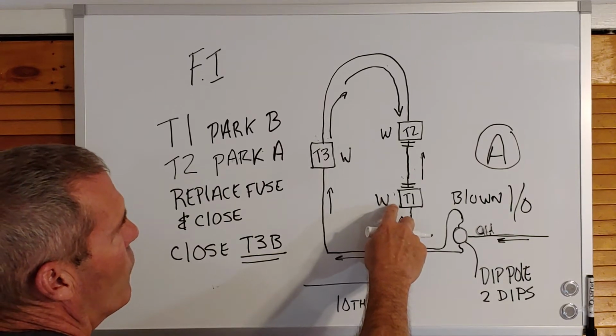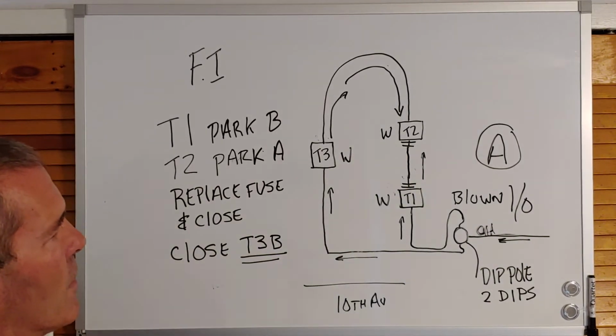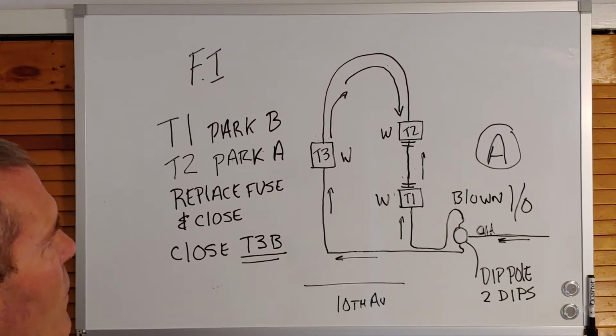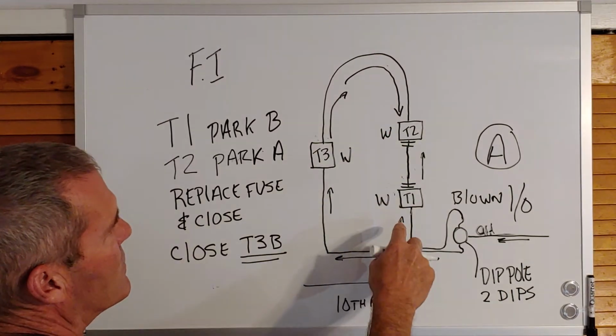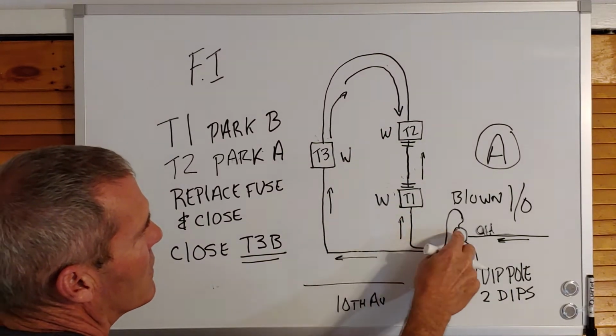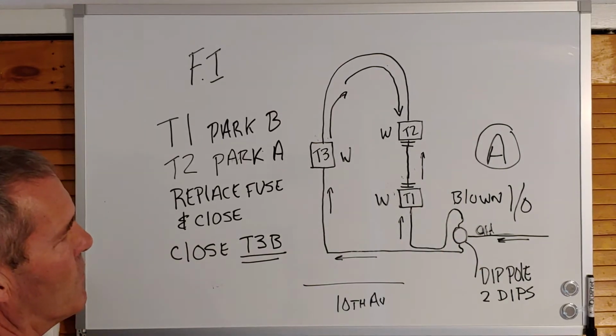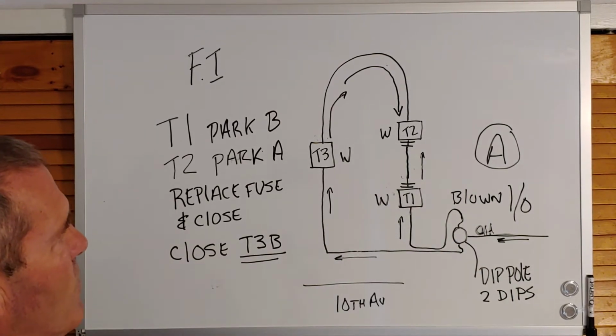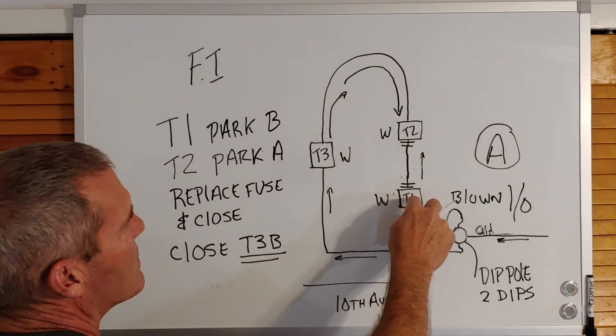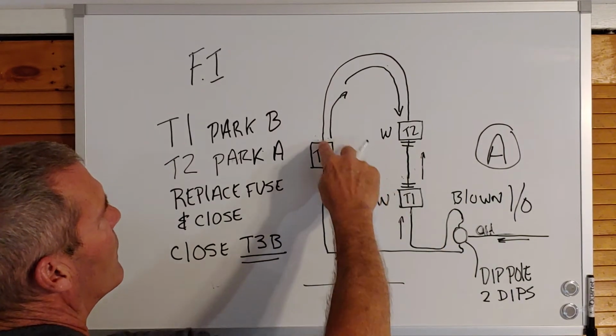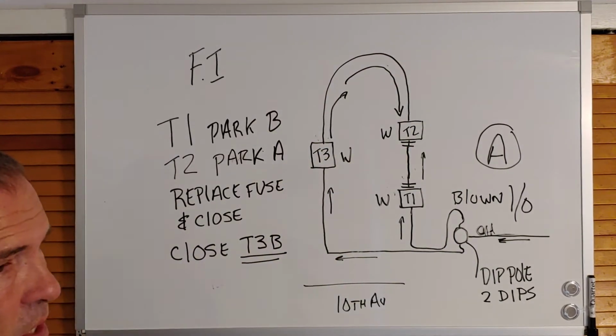Well, I've got a white and a white. Then you can tell your lineman out the road, hey, I've got 2 white indicators at T1 and T2. Looks like it's in the first span coming off the dip pole. Then you guys are just going to team up together and come in, isolate the span, and backfeed. It's going to be a team effort.